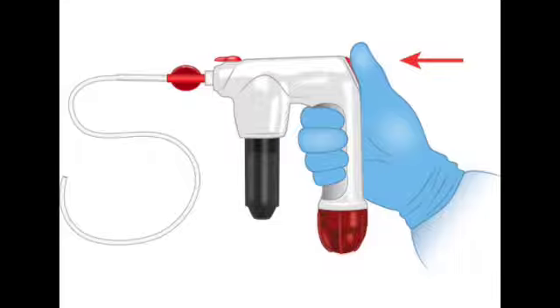And the activation is this very deliberate multi-step sequence. The doctor first turns a knob at the base to pierce and activate the CO2 cylinder. Then they open a directional valve, which primes the pressurized gas to enter the catheter system. And only then are they ready to actually pull the trigger. But this isn't like spraying a fire extinguisher, is it? You don't just hold the trigger down. No, not at all. You have to remember, you're pushing a heavy, dense mineral powder through 3 feet of a headphone jack-sized tube. The physics of that delivery require a really specific firing strategy.